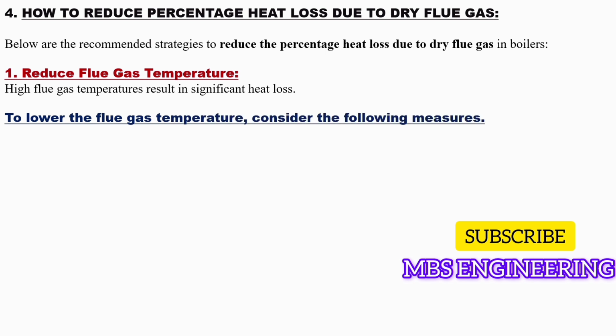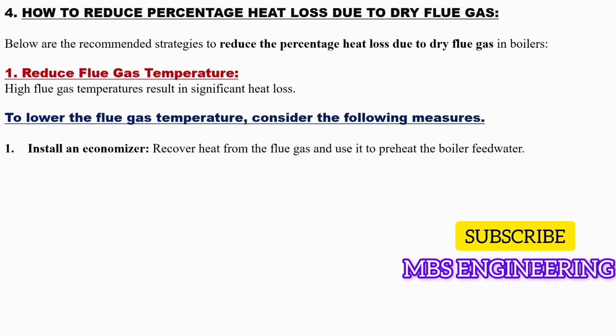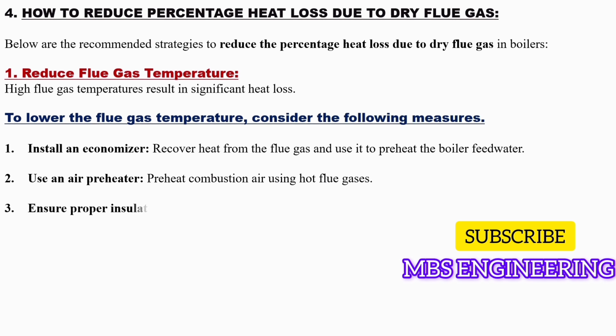To lower the flue gas temperature, install an economizer. Recover heat from the flue gas and use it to preheat the boiler feedwater. To lower the flue gas temperature, use an air preheater. Preheat combustion air using hot flue gases. To lower the flue gas temperature, ensure proper insulation. Insulate the combustion chamber and ducting effectively to minimize heat loss.